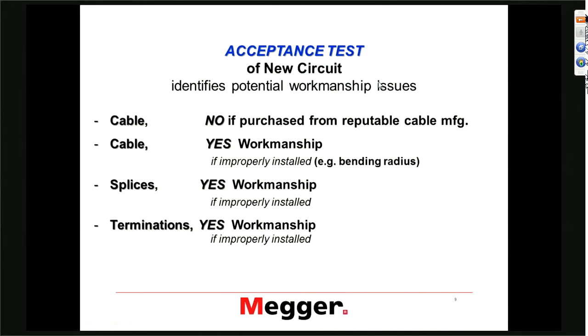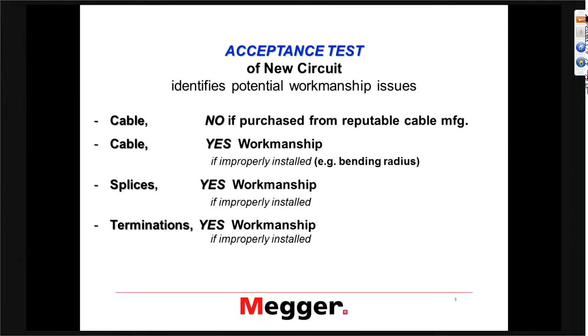Acceptance testing of new circuits is done mainly to identify potential workmanship issues. The components we have in the circuit are the cable. Typically we don't have much concern about a new cable if it's purchased from a reputable cable manufacturer. Cables have improved in quality — especially extruded cables, which represent the majority of cables used today — substantially over the past 20 years.